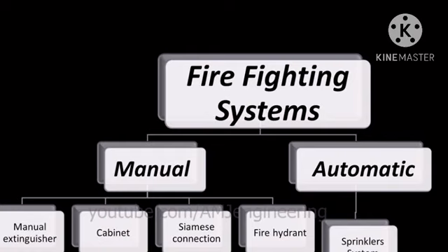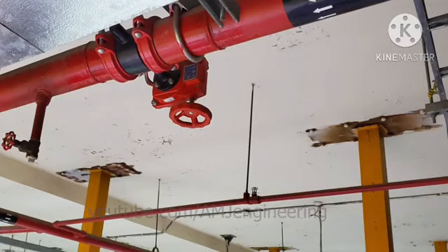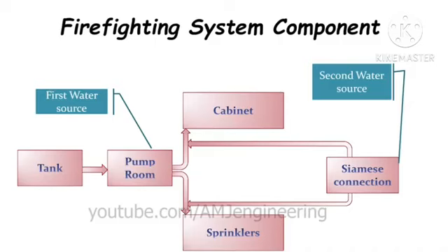An automatic system, as its name says, fights the fire automatically without the intervention of a human being, and that's what a sprinkler system does. Here is a schematic diagram of the system components. Usually both systems exist in all buildings to form a competent firefighting system matching the NFPA standards. So, in any building, the system consists of three basic parts. A large store of water in tanks, either underground or on top of the building, called fire storage tanks.